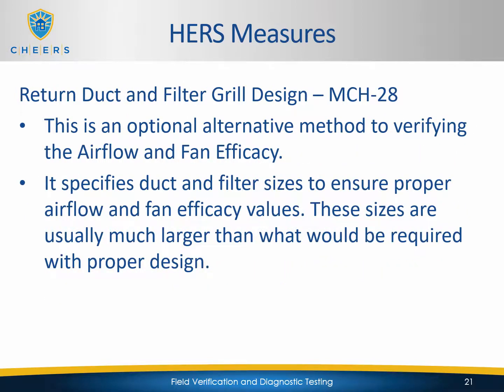Return duct and filter grill design is going to be on the MCH-28. This is an optional alternative method to verifying the airflow and fan efficacy. A few slides ago, we were talking about airflow and fan efficacy and how we're going to measure how hard the fan is working and make sure that enough air is flowing across the evaporator coil, so we're reaching those efficiencies that we need. Well, this is an alternate to performing those tests. The contractor can say, I'm going to take this option, and then as the HERS rater, you're not going to do airflow and fan efficacy testing.